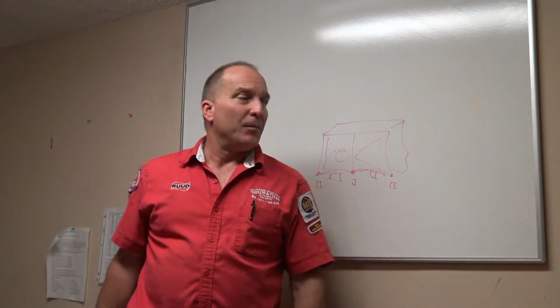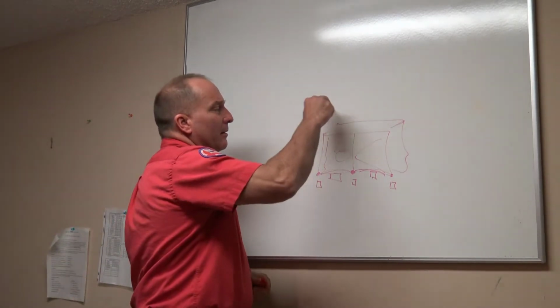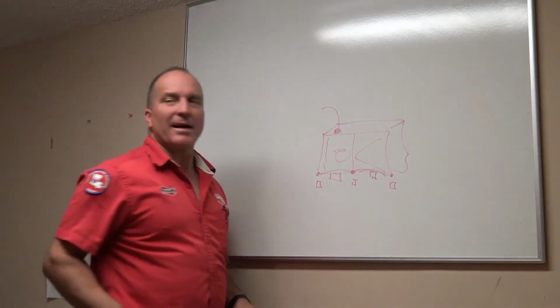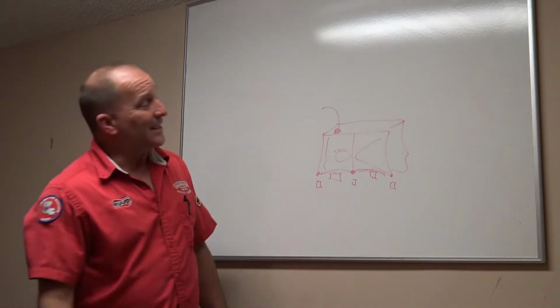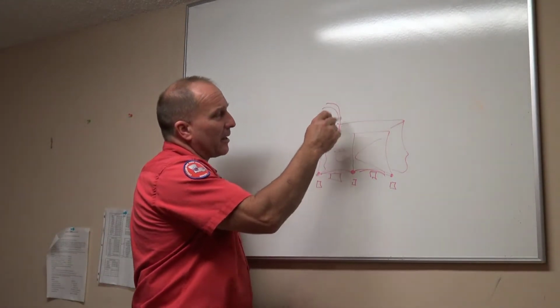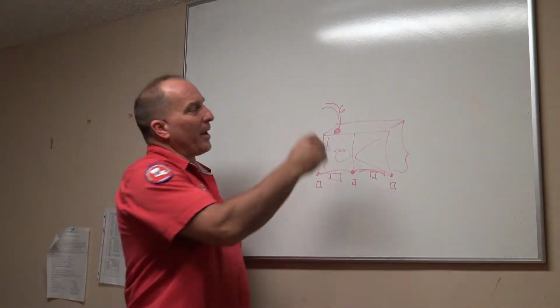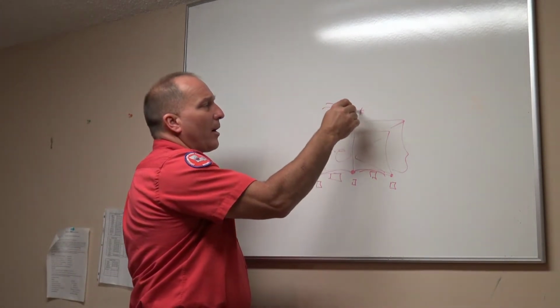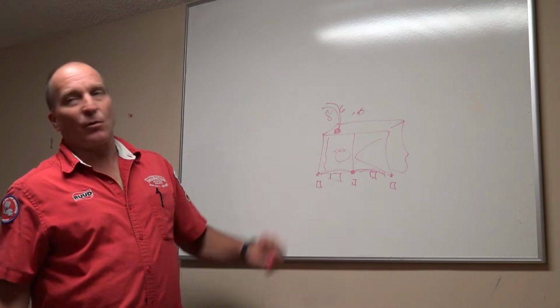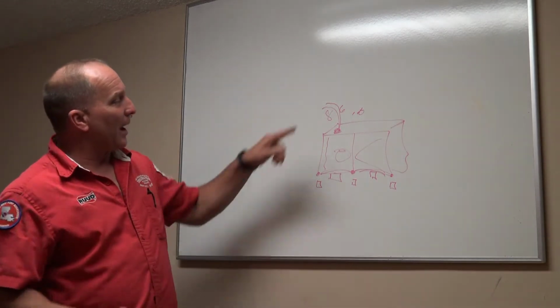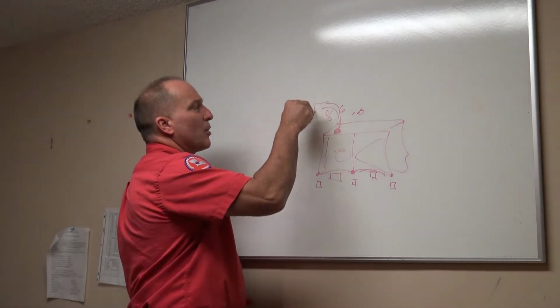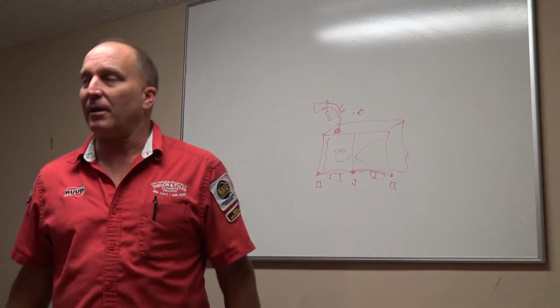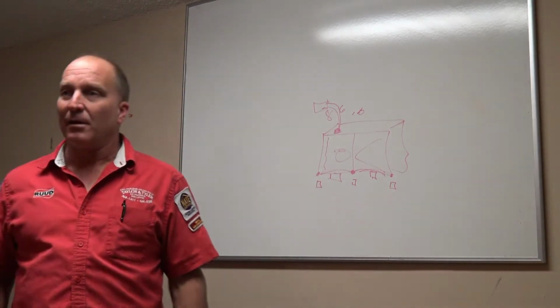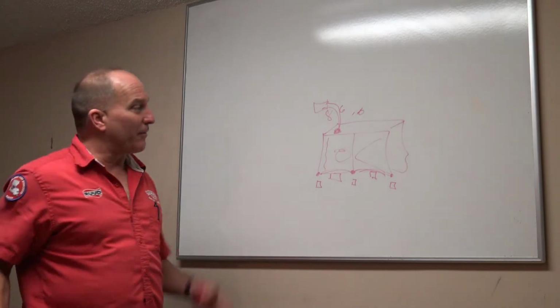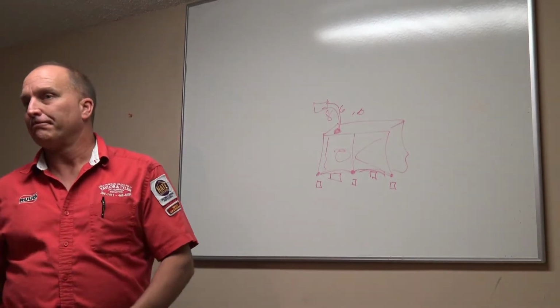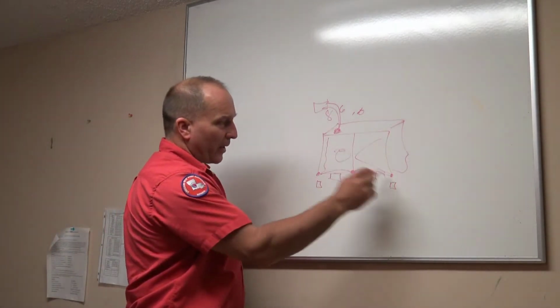Okay? Does the wire coming in here have a Romex connector on it? What size wire is coming in here? Is it a number 6 wire? Is it a number 8 wire, 10 wire, 4 wire? What is it? Does it have a Romex? What size breaker do you have coming from here? So when I'm asking you the condition of the air handler, I'm actually asking you the condition of the whole install, aren't I? Yeah. Not just the physical box right here, right?